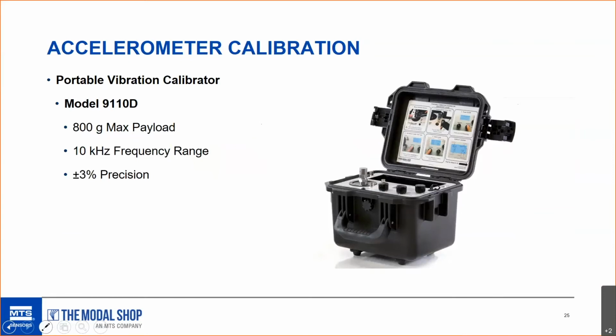Yeah, so portable vibration calibrator: 800-gram max payload, 5 to 10 kilohertz frequency range, plus or minus 3% precision. Not the most accurate calibrator on the market or that we have to offer, but it's portable. So a lot of plants will use this device to loop check the vibration monitoring system and test alarms, which you'll see in a video that's upcoming in the presentation. So we'll hold off on what it really does until we get to the video. If you're thinking about accelerometers today, you should check out all the videos Mike has put up with the portable vibration calibrator.